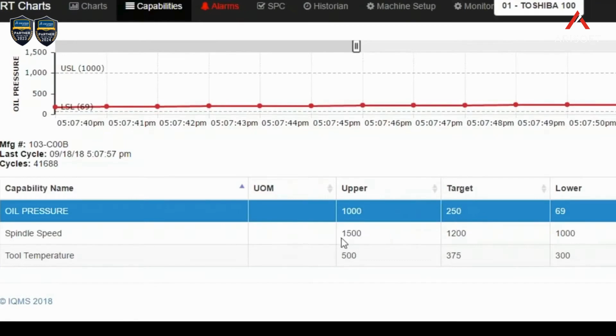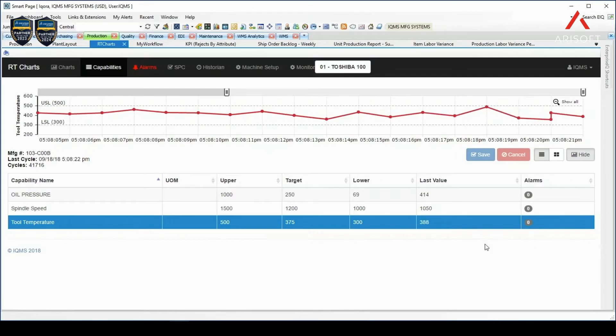For oil pressure, we've set a lower and upper threshold with a target parameter. The same has been set for both spindle speed and tool temperature. We can then track activity on the machine in real time, and the PLCs generate live data points to view and analyze. Should the tool temperature fall below the lower threshold of 300 or go above the 500 mark, the system will trigger an alarm, giving shop floor employees a chance to immediately address the issue.